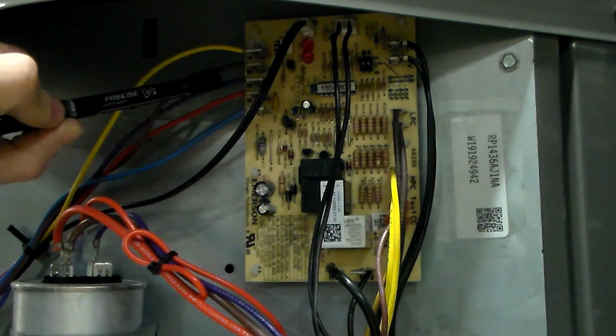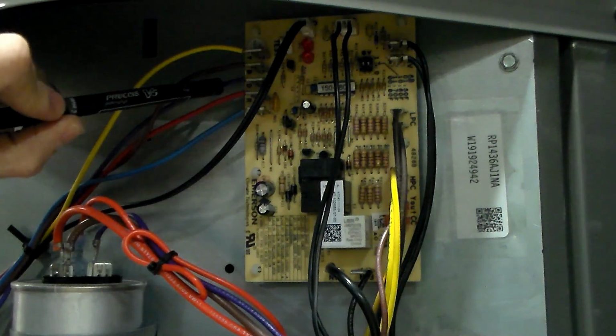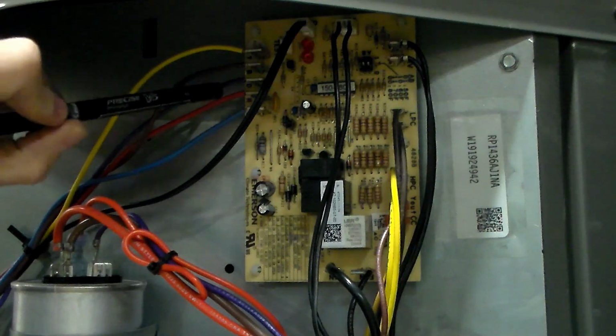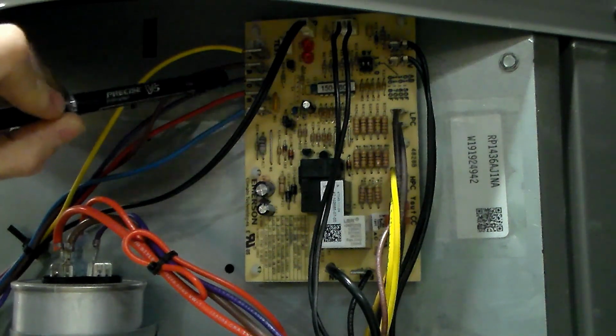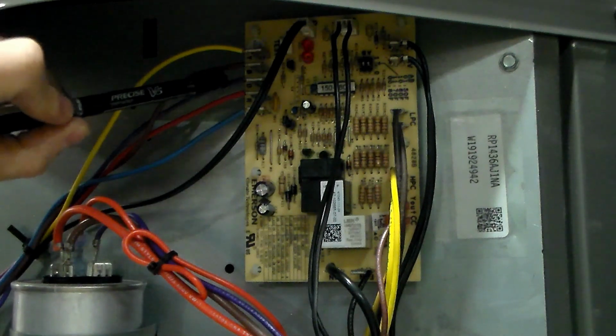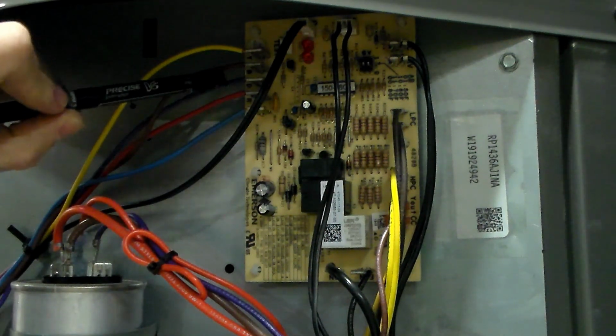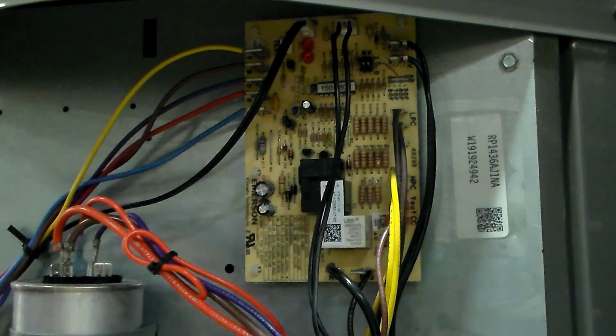The other thing that we saw is different is it's got a D instead of a W, and that just stands for defrost. It's going to work exactly the same way. That's going to send your W signal in during defrost to temper the air so you're not blowing cold air on the customer during defrost.